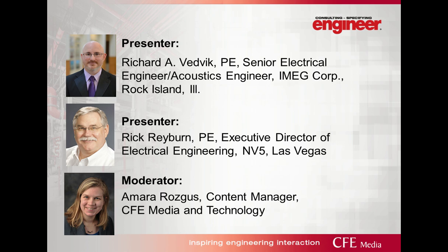For this, consider back to NFPA 110. And what is a flywheel source? Does it comply with run times? Remember, your types and your classes are going to tell you it's great for an uninterruptible power supply source, but is it going to last 15 minutes, an hour, 4 hours, 48 hours? Whether or not it's legal is going to depend on how long it can run. And in most cases, flywheels are really just to ride through while the generators are getting started.